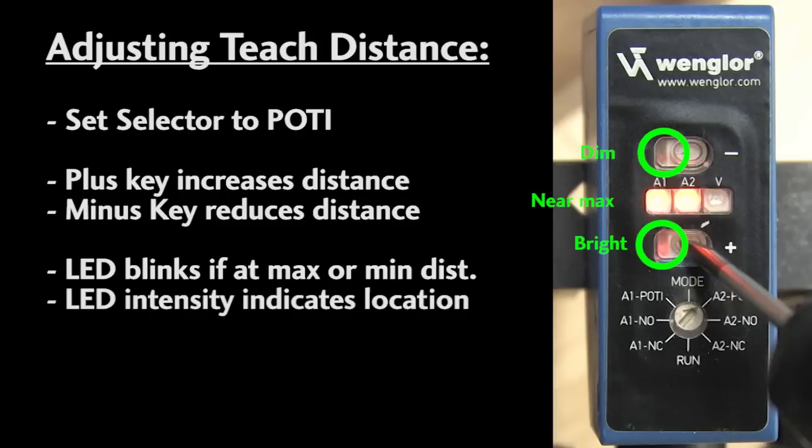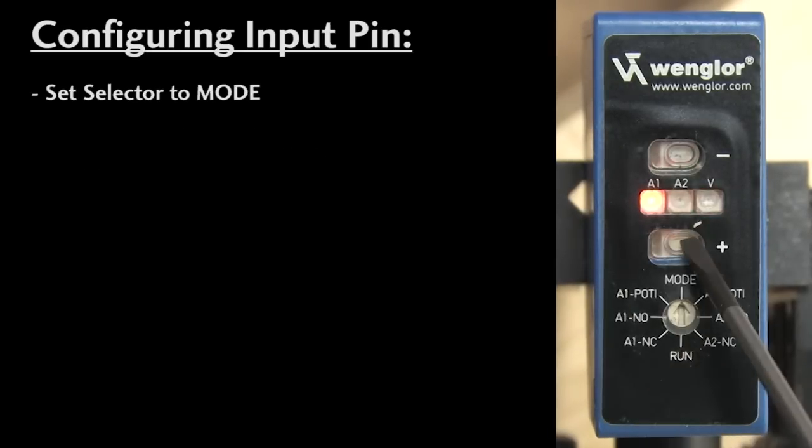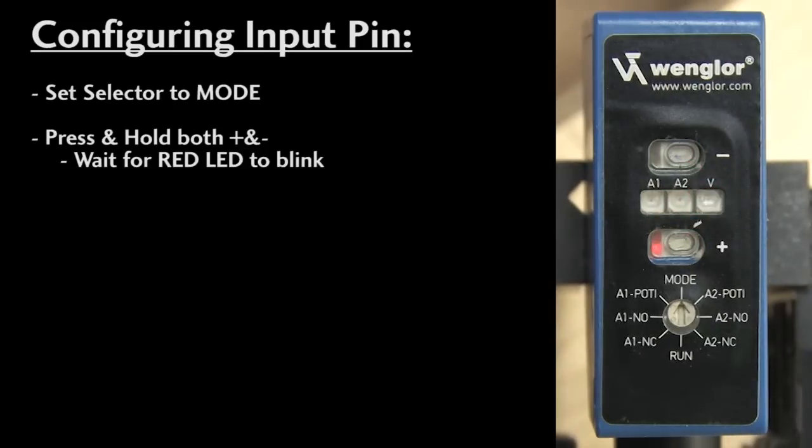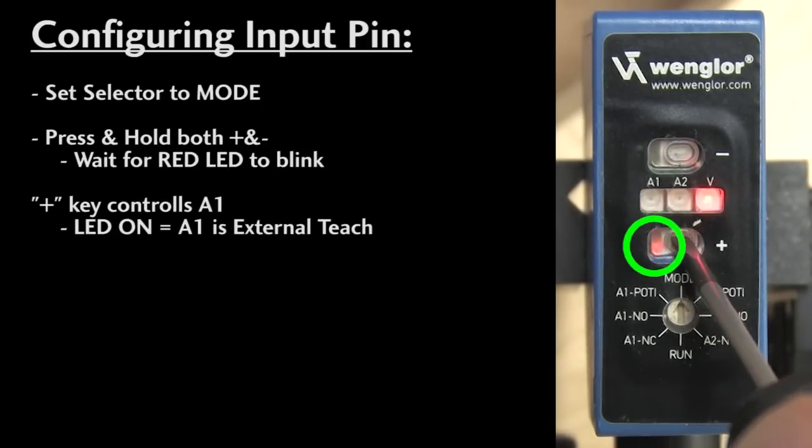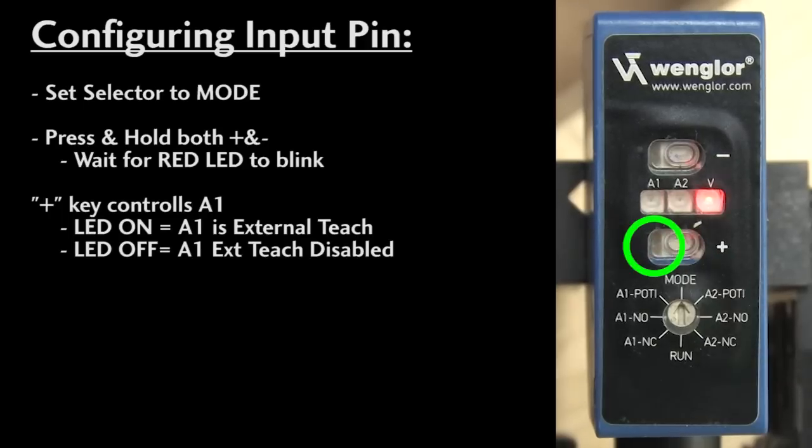To configure the input pin, set the selector to mode and press and hold both the plus and the minus keys until the red LED blinks – it will take about 5 seconds. The plus button controls A1. If the plus LED is lit, that says that the input pin will be used for external teach of pin A1. If the LED is off, the external teach is disabled for output pin A1.